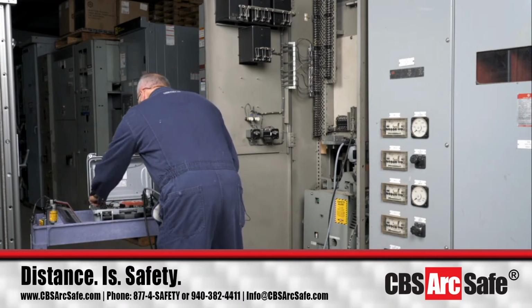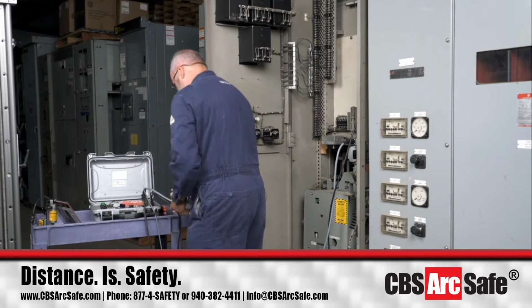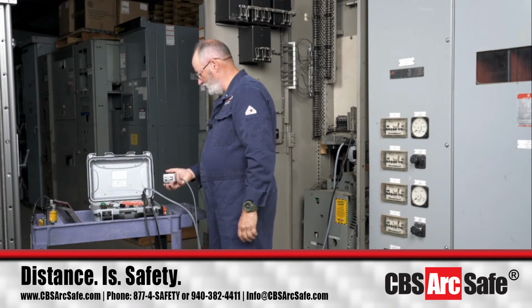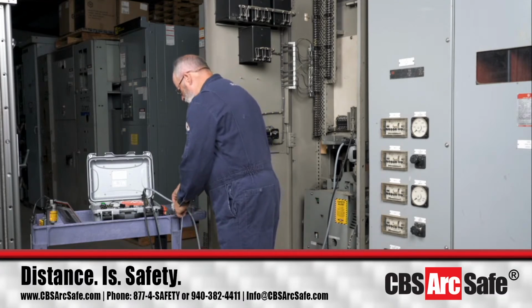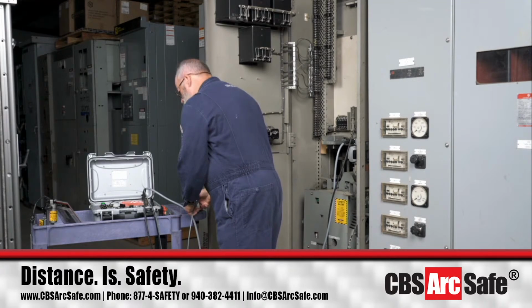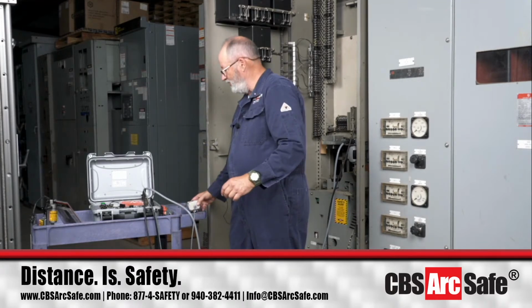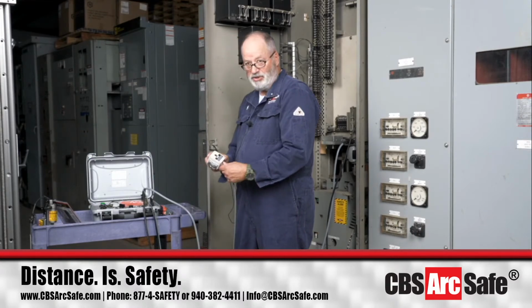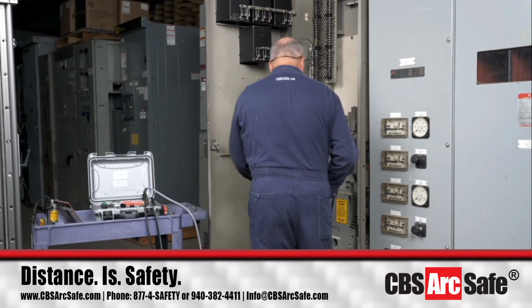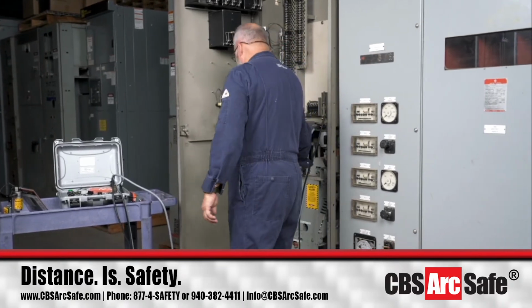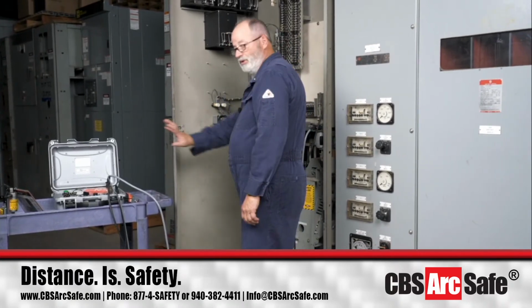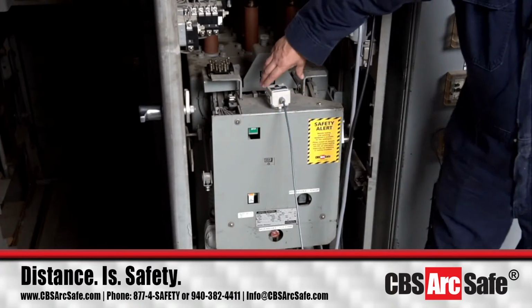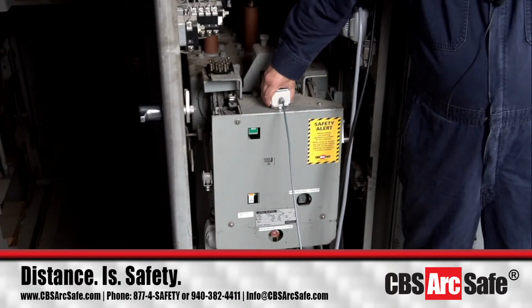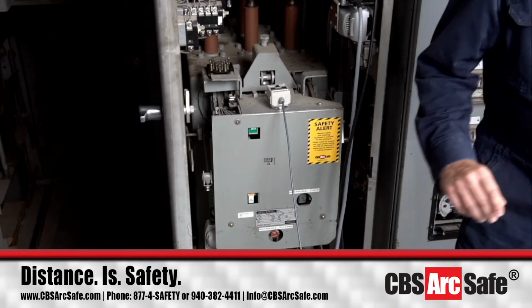All right, now I'm going to go power on local, and I'm going to zero out my tilt switch here. There, I got it. So any variation of 10 degrees is going to set the tilt switch off. When I put this on the front of the breaker like this and zero it out, you see the light starts going off. If I rotate it just 10 degrees any direction, front, back, left or right, that's going to happen.